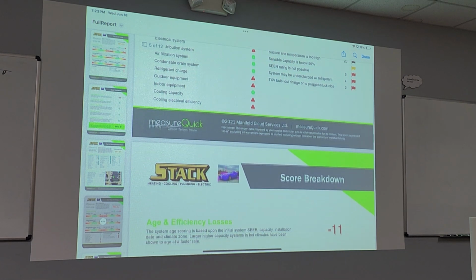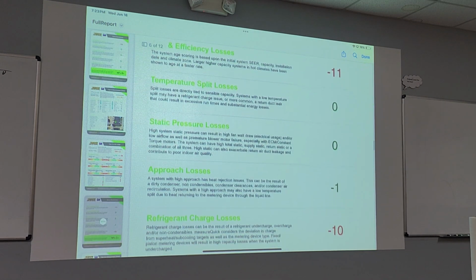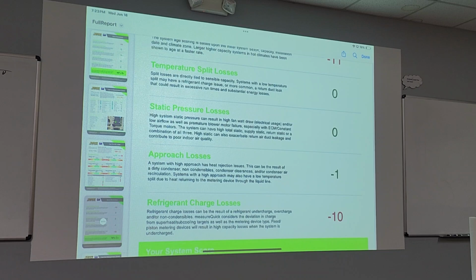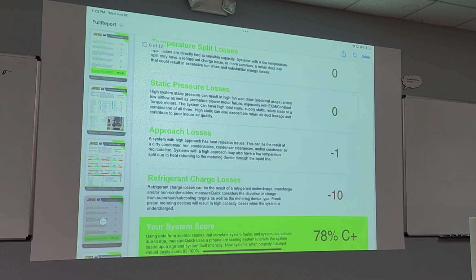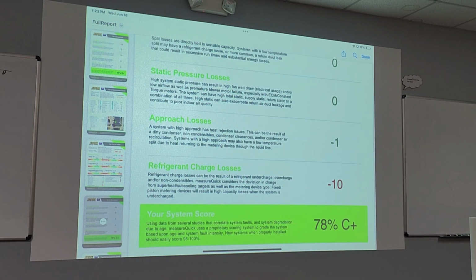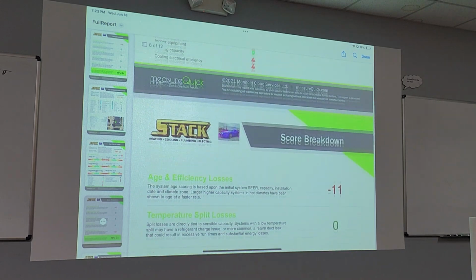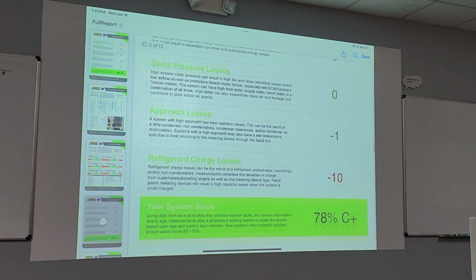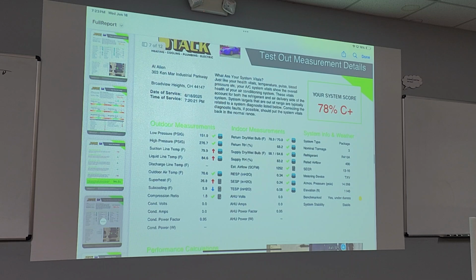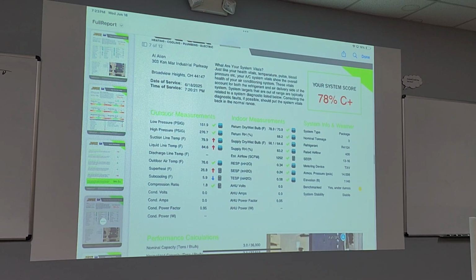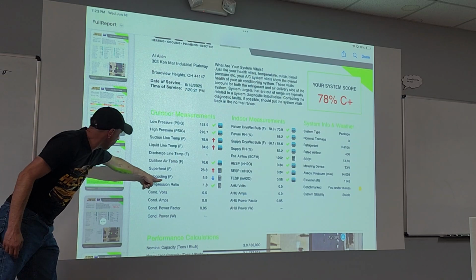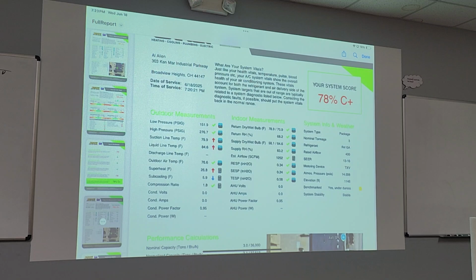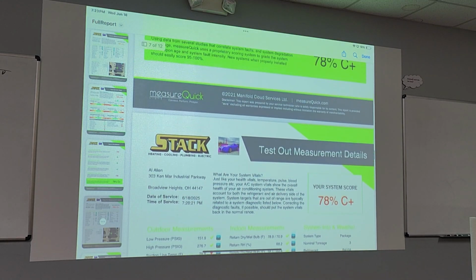Well, if you remember, I was teetering on the brink of refrigerant charge being out of range, and it just happened to jump out of range when I hit the button. So now, what's my subcooling? My subcooling dipped down to 5.9. Right here - because the subcooling took a dip right as I hit the button, it took my score down even lower.